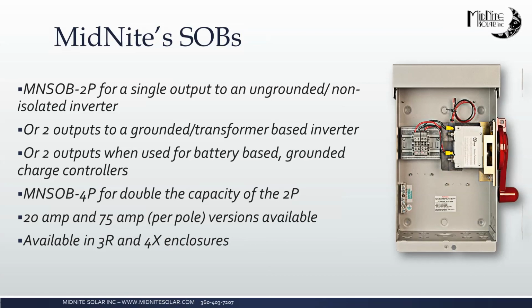So if you had maybe a 10 kilowatt SMA inverter and you needed to disconnect but you did not need to combine, you could use the 4-pole 20 amp version. Or if you needed to disconnect, say, 4 Classic 250s or Schneider XW 60 amp charge controllers for rapid shutdown and you needed something to deal with the bleed down, you could do the 75 amp version on the input of that, put the PSB up in here that we'll talk about later, and interface with our birdhouse.